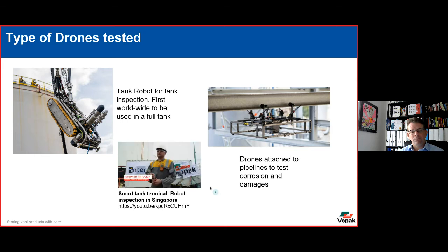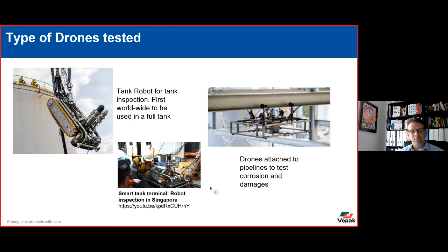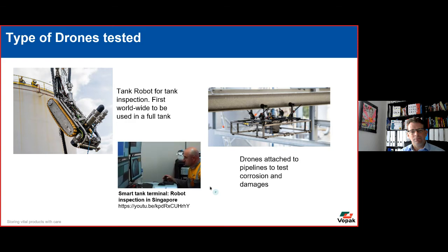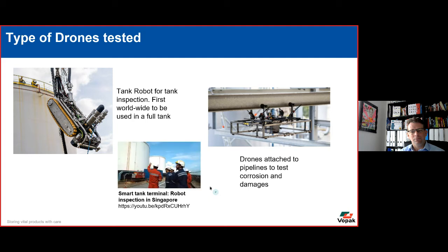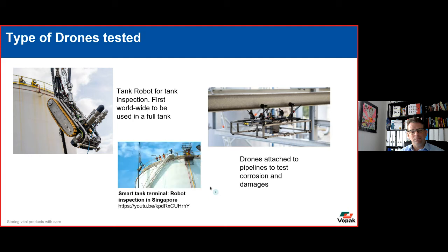We place safety first. Some of the design features that we have in it are the flame-proof enclosures, the pressurized enclosures, the purging and pressurizing with nitrogen. We make sure everything is done in a methodical, safe method. We are pleased with the outcomes of this trial at the Sebarok Terminal. This trial is able to yield high amounts of valuable field data not found in a test environment. We have certainly gained valuable experience for deploying in-service robotic tank inspection technologies at more Vopak locations.